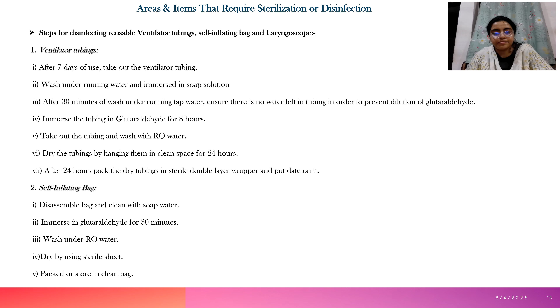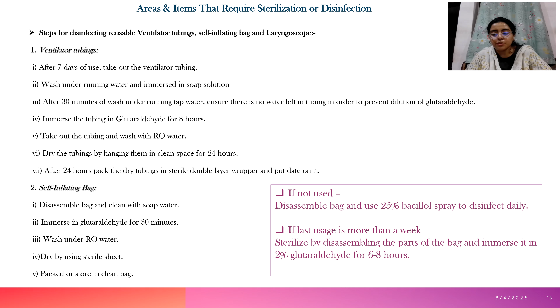Self-inflating bag. Disassemble the bag and clean it with soap and water. Immerse it in glutaraldehyde for 30 minutes. Wash under RO water. Dry by using a sterile sheet and pack them for further use in a clean and sterile bag. If the self-inflating bag is not being used, we have to disassemble the bag and use 25% bacillol spray to disinfect daily. If last usage is more than a week, sterilize by disassembling the parts of the bag and then re-immersing in 2% glutaraldehyde for 6 to 8 hours. This has to be done once per week if the bag has not been used for more than a week.